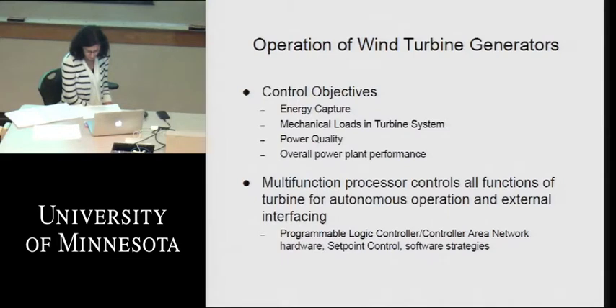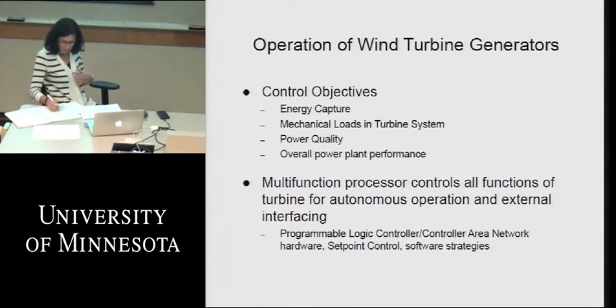And it could take a certain amount of fluctuation that, if you were, say, 200 miles away from any other generating resource that could help to strengthen your immediate electrical system, and hence your system is very weak that you're pumping your power into, then small fluctuations in your power and voltage and frequency would cause large fluctuations in that portion of the grid. So the grid is not all homogeneous from coast to coast. It is strong in some areas and weak in other areas.